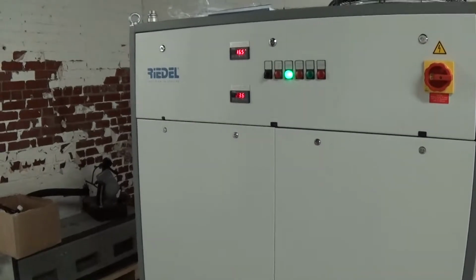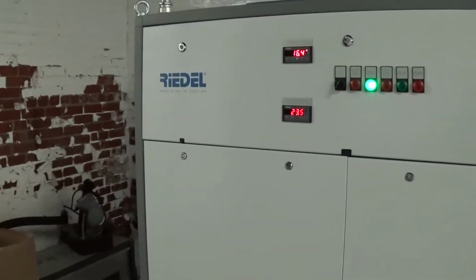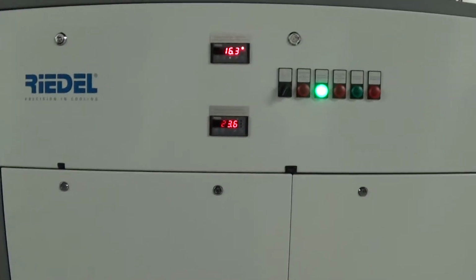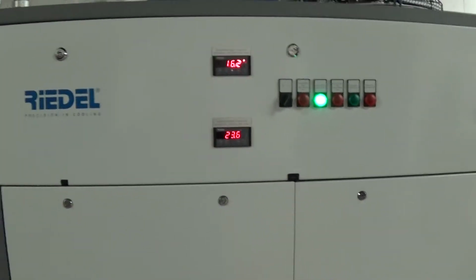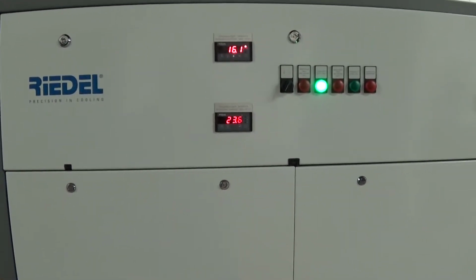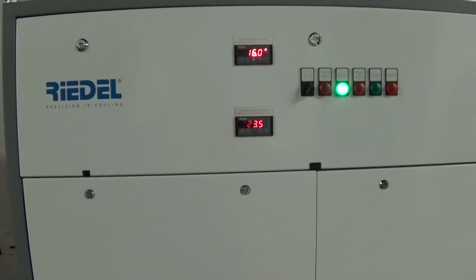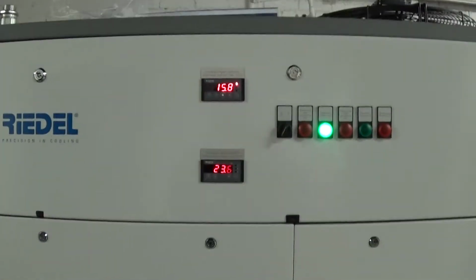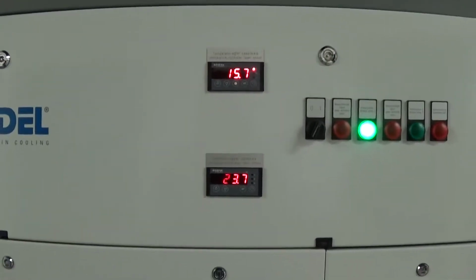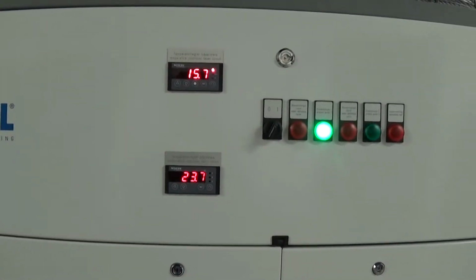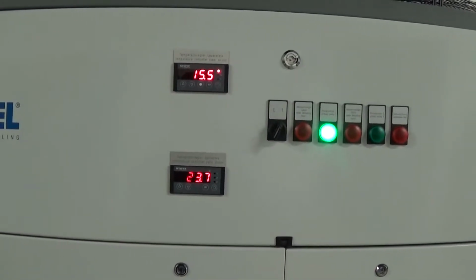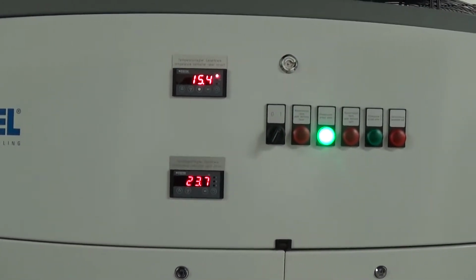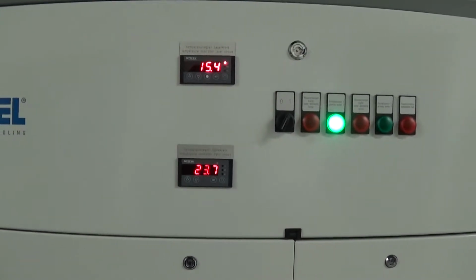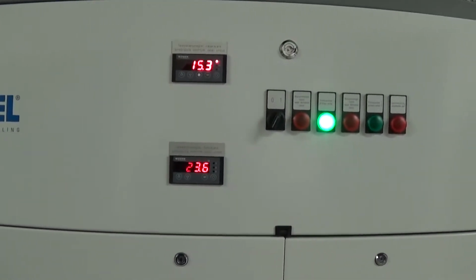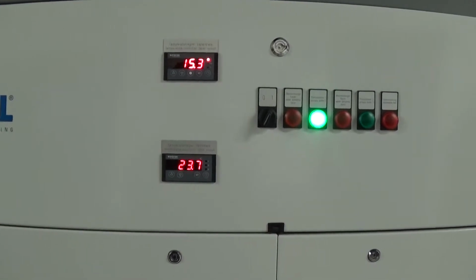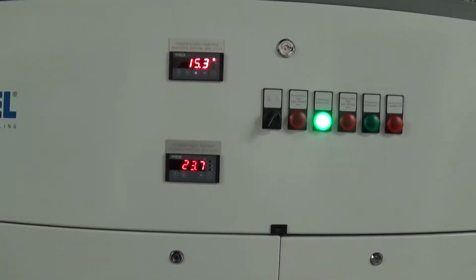Again, in the process cooling world, it is desirable to keep compressors running a fair amount of time, and in some cases as long as possible, or always on, even with a reduced load. But let's see here as you hear that hissing noise. So now we've got the hot gas bypass turned on, and we're cooling relatively quick, and that's a fairly sizable tank because we are up at 24 C. That hot gas bypass will come on and it'll start effectively slowing down that rate of cooling to keep the compressor running longer.